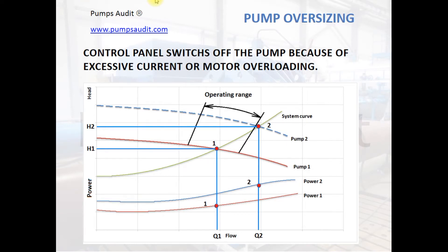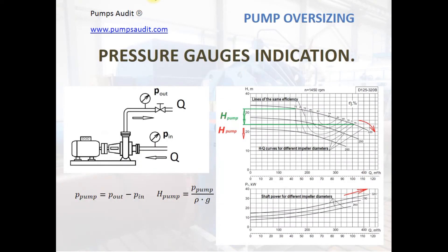Very often the pump user cannot understand what happens, and thinks the pump or electric motor is defective. By using pressure gauges, the pump user can define the position of the operating point relative to the operating range. This is another way to determine if the pump is oversized. If the pump is oversized, it will have a head less than the head within the operating range. Try closing the discharge valve and see what happens — how will pressure, current, vibration, and noise change?